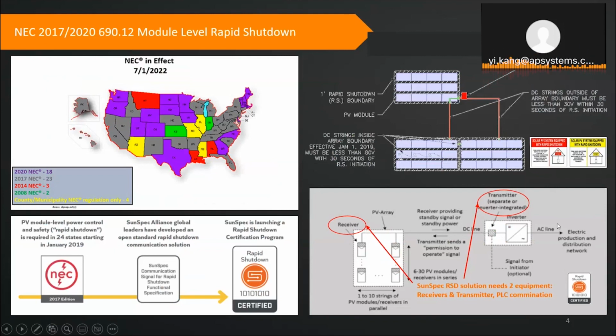So what happens in the system: when you turn on the grid, the AC is on, your inverter is turned on, and the transmitter starts to generate the signal. The signal is transferred through the DC line to the receiver. When the receiver receives the signal, which we call the heartbeat signal, it becomes alive, meaning it releases the power from the PV panel. In other words, by default, this device will cut your power from the panel. That's the most common question we get from installers: why does my PV panel have no power output after installing your device? That's supposed to be the case, actually.